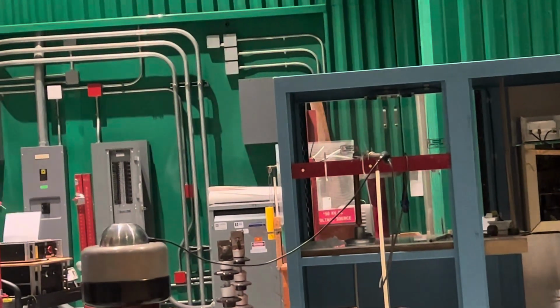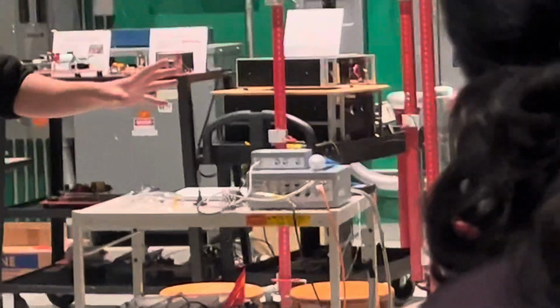We also use high frequency current transducers or antennas to detect those PD events. When we need to do a low pressure test, we may place a chamber on this bench.